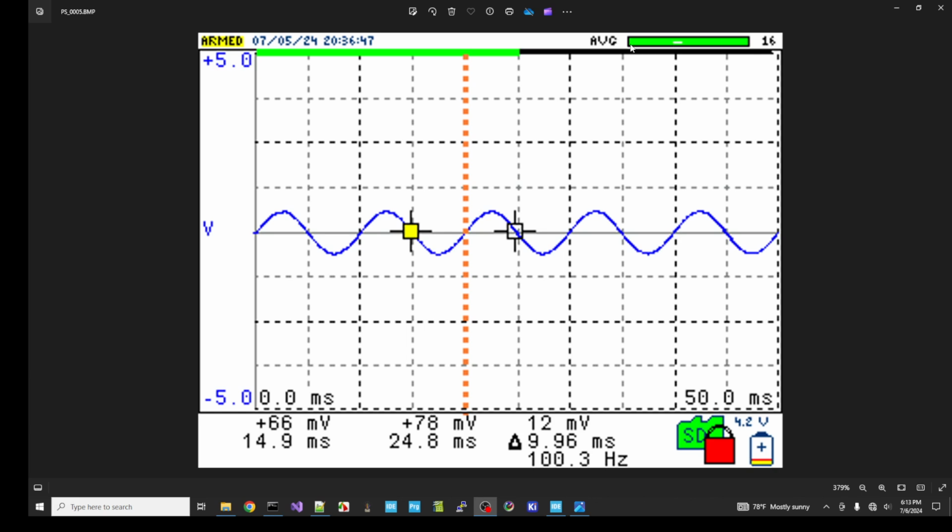This bar in the upper right hand corner may or may not be there depending on how you have things set up. This indicates that you have averaging selected, and you've selected 16 averages, and this average can be either set up to be kind of like a fixed length where you do 16 averages and stop, and then you would be done. And when you hit 16, which is like this has got 16 because it's fully green, this would have changed from arm to hold if it was a linear fixed average. But I have a running average, so I've got 16, but I continue to collect data, and you'll see this little white dash kind of zoom across here periodically as it's continuing to collect data.